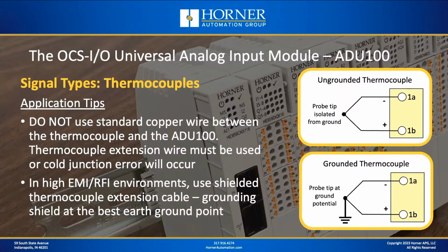With thermocouples, extension wire is another factor you need to consider in your application. You might be tempted to use standard copper wire between the thermocouple probe and the ADU100 to connect the two. Bad idea. You will get a cold junction out in the field where it can't be compensated for, and your readings will be way off. Instead, use thermocouple extension wire between the probe and the ADU100. That's true with really any thermocouple measuring instrument, not just the ADU100. So if you're using a Type K thermocouple probe, you should use Type K extension wiring. And if you have a noisy environment, you should use shielded thermocouple extension wire and properly handle the shield. Remember, we're only talking about a signal that's a few millivolts in magnitude.